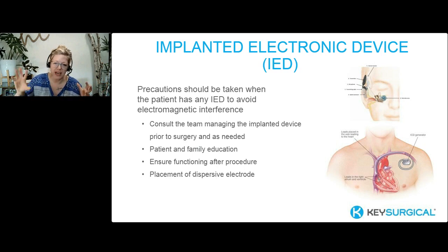We want to create that circuit. We don't want the electrical current to have to go through that device in order to exit the body. So that's why we put it as close as possible to the surgical site, on the same side as the surgical site. We really want that path to be as short as possible, not going through any device.